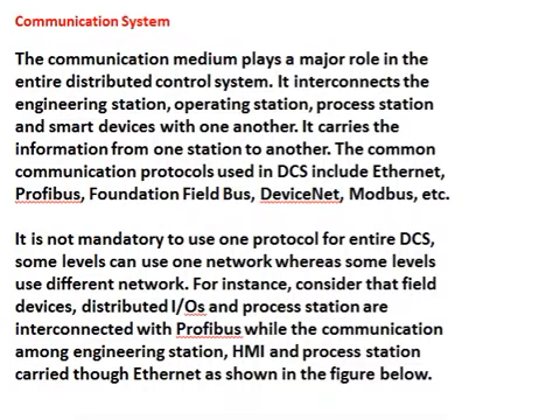Communication system. The communication medium plays a major role in the entire distributed control system. It interconnects the engineering station, operating station, process station and smart devices with one another. It carries the information from one station to another. The common communication protocols used in DCS include Ethernet, Profibus, Foundation Fieldbus, DeviceNet, Modbus, etc.